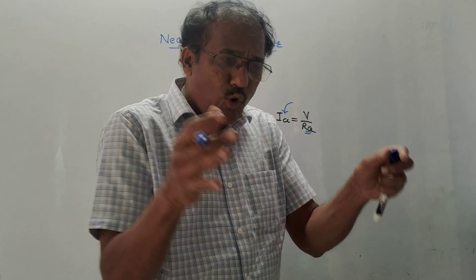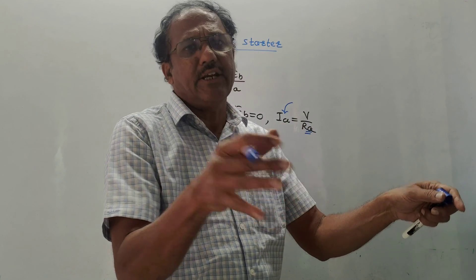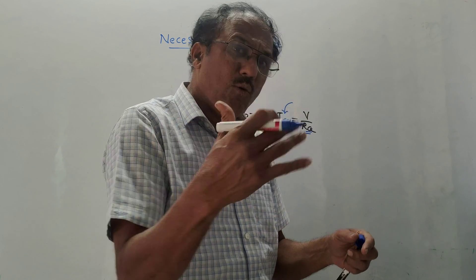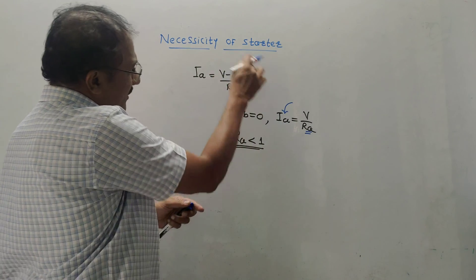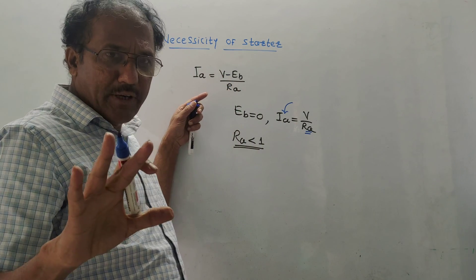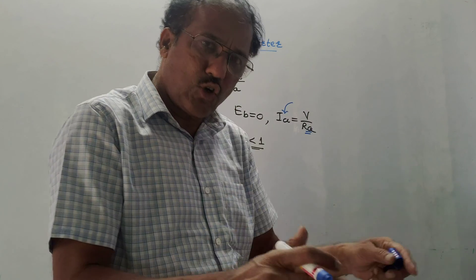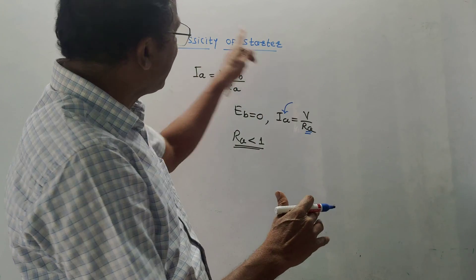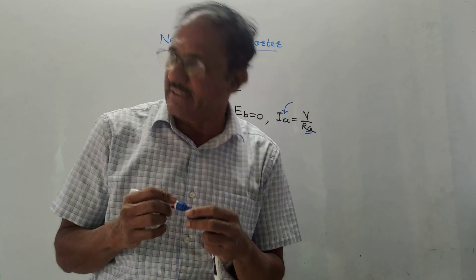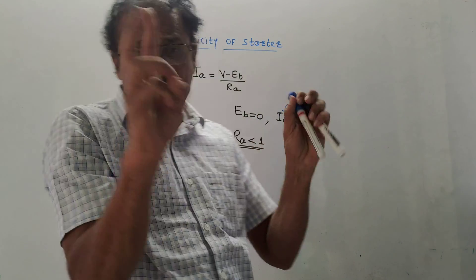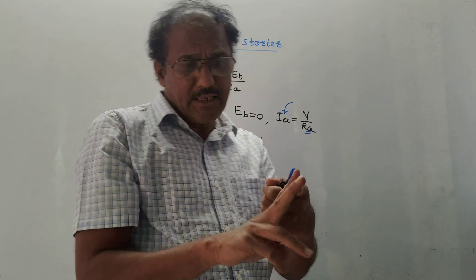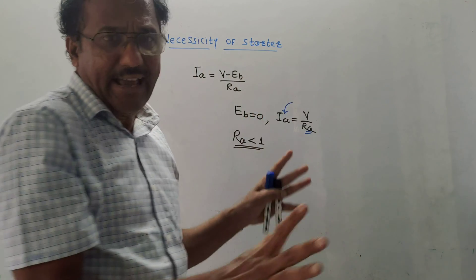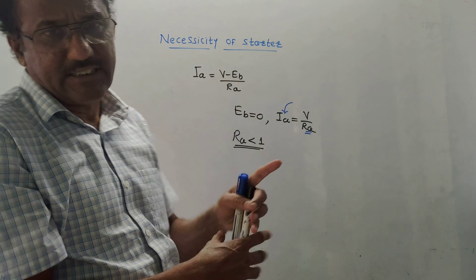To limit this current, starters are required. The basic concept: to limit current, connect some extra resistance in series at the beginning. After that, once the back EMF is generated, the armature current will be controlled. So starters produce extra resistance in series with the motor only at the starting point. There are two types: three-point and four-point starter.